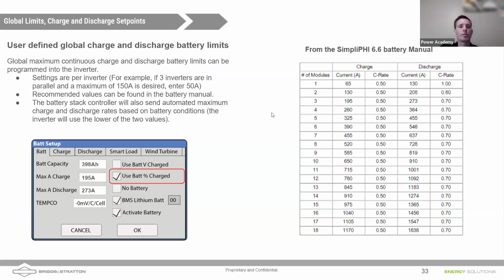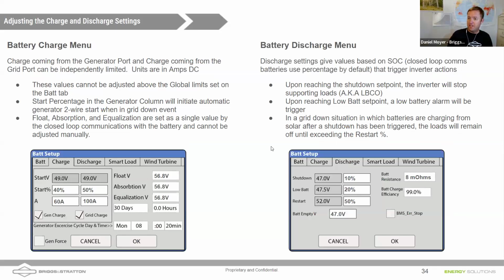But if you have parallel inverters, it's per inverter. So if you wanted to hit, let's say, the 585 that Daniel mentioned, the most you could do is 275, which is what you would program the master inverter to be. And then it would be double that because you have 2 inverters both kicking out 275. We get 550 on a 15K, pretty close.